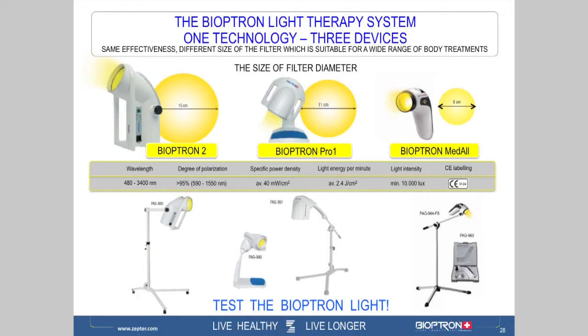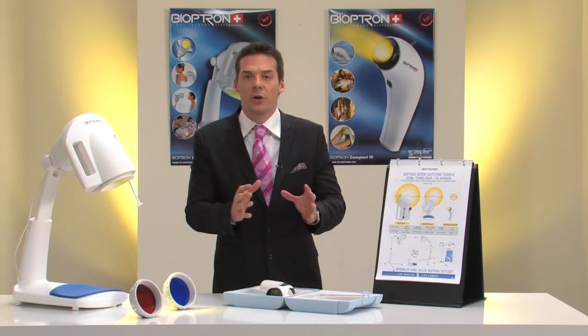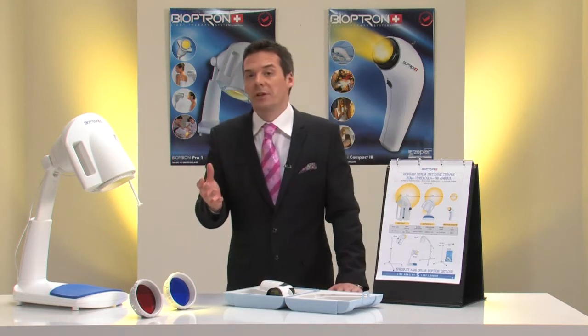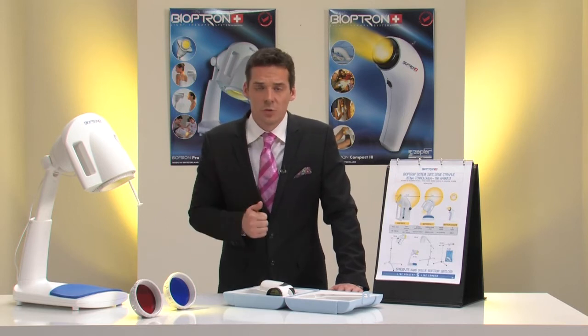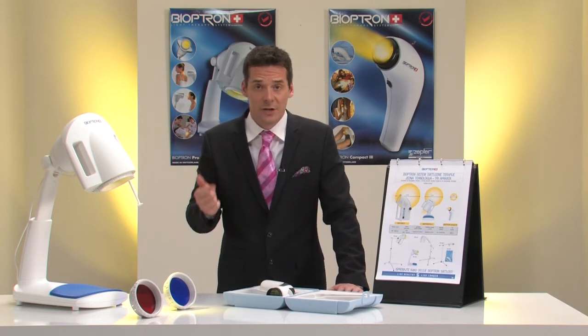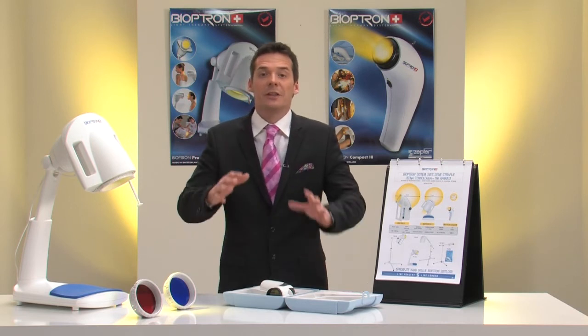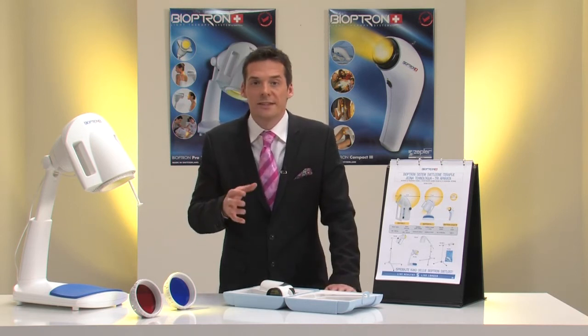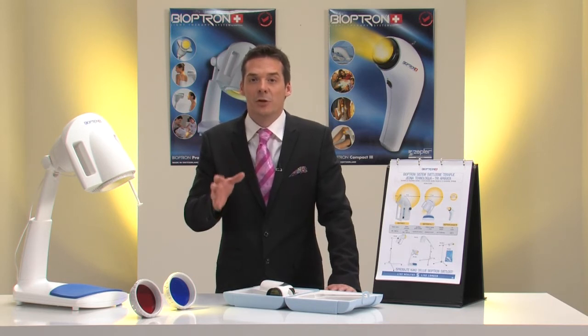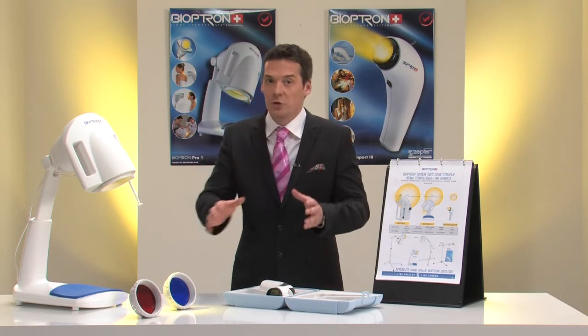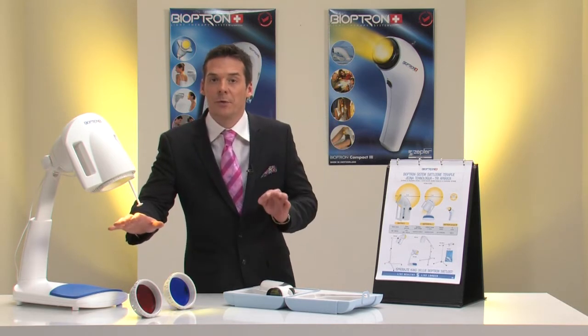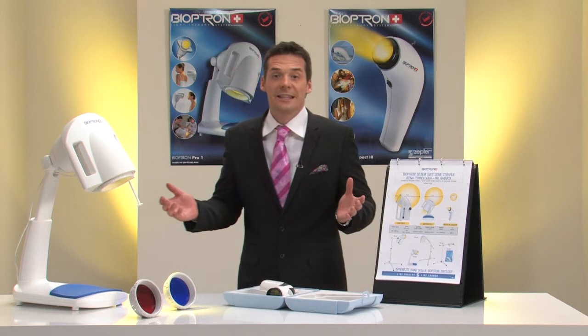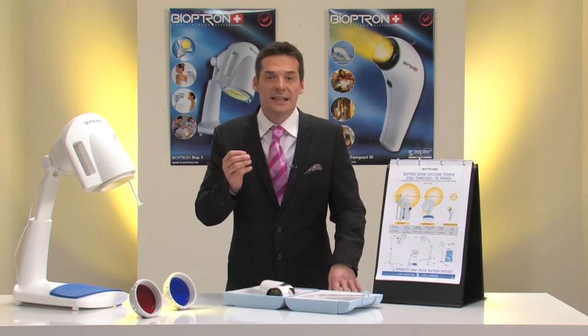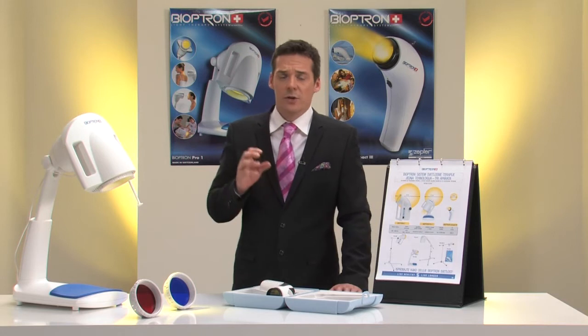There are three different models of BIOPTRON medical device: BIOPTRON 2, BIOPTRON Pro 1, and BIOPTRON MedAll. All three models feature the same technology, they look the same, and they are equally effective. Their wavelength ranges from 480 to 3,400 nanometers. The level of polarization is the same, over 95%. The specific power density is 40 milliwatts per centimetre square, meaning they have the same dose of light energy of 2.4 joules per centimetre square per minute. They have the same light intensity of 10,000 lux minimum needed for the treatment of SAD. The only difference is the size of the filter diameter.